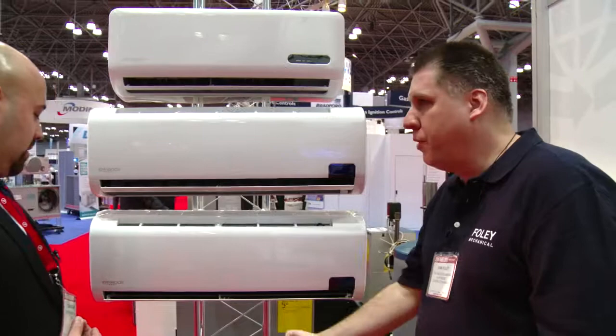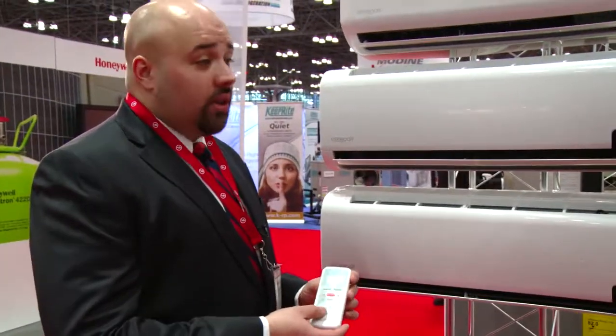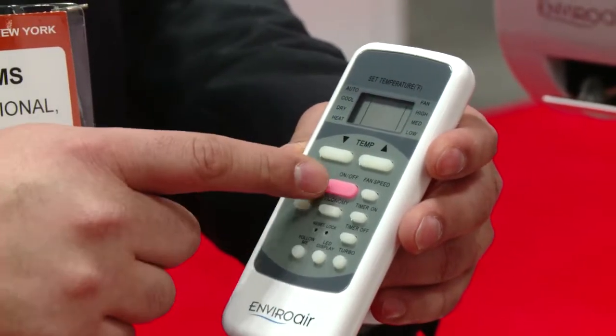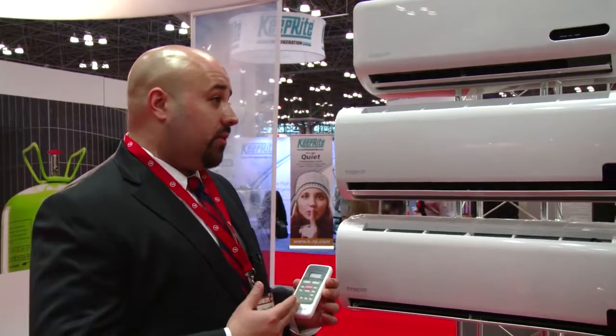Talk about the zoning. You've got a wireless remote control. Is that how you control these? Yes. The infrared remote comes with every single air handler as a standard. We actually have a feature we like to publicize. It's called Follow Me. The remote acts as a remote temperature sensor. So the air handler actually conditions to where you are located in the room. The default is the temperature sensor within the air handler itself, and if the air handler doesn't see the signal coming from this remote, it'll revert back to the air handler temperature sensor.